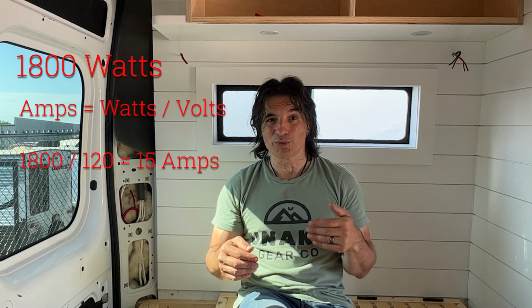Now 1800 watts divided by the voltage, which is 120, gives us 15 amps. So we know we could actually run that circuit on a 15 amp circuit. It's probably a little close to the top, so we're probably going to do a 20 amp circuit for that one. The water heater is the other big device.